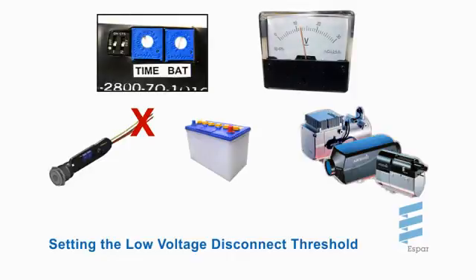Disconnect the power before setting the low voltage disconnect presets. This switch can be preset from 10.5V to 12.5V in increments of 0.25V or from 21V to 25V in increments of 0.5V.